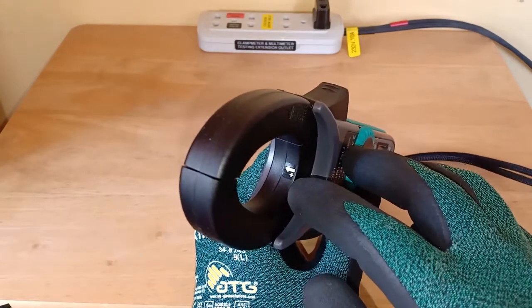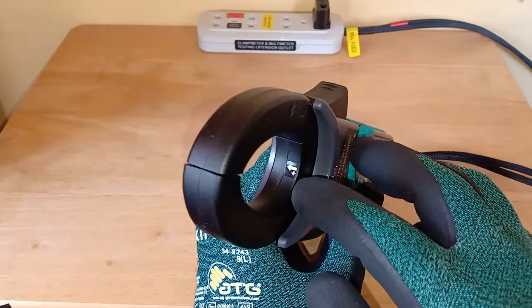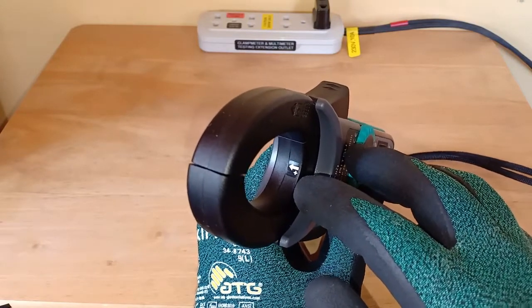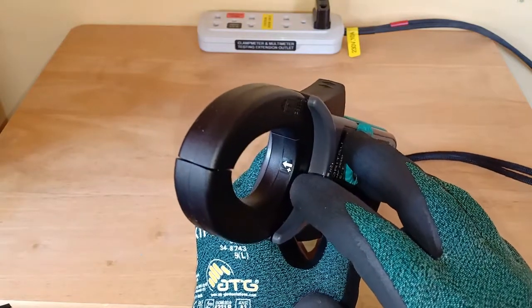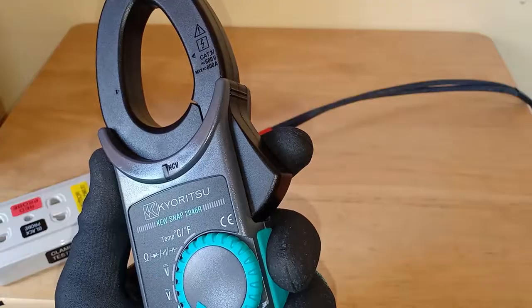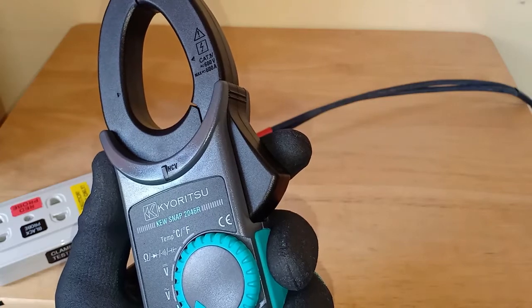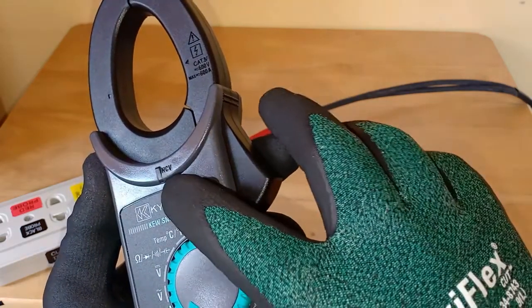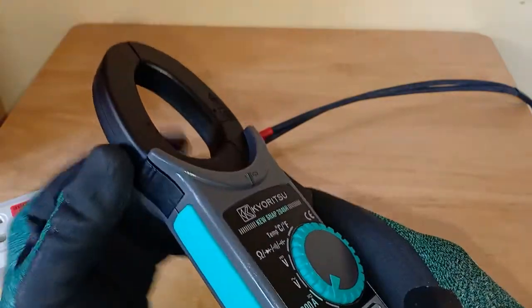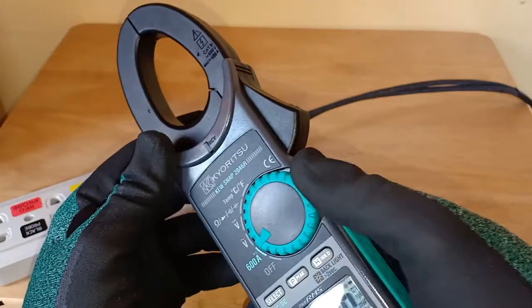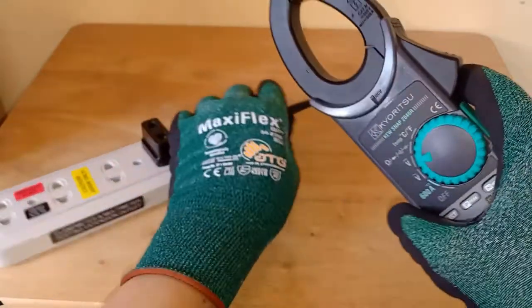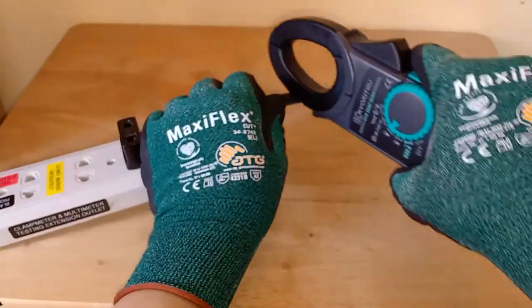This is used for properly orienting the clamp meter with the direction of the load when clamping the positive line. For AC current measurement, these are not necessary. It also has a non-contact voltage detection function, indicated by this red LED light, and the sensors for that are installed in this area. The NCV is automatically enabled whenever the device is turned on.